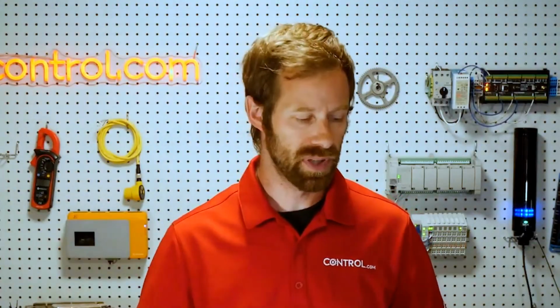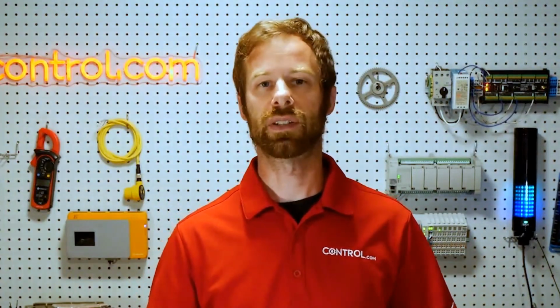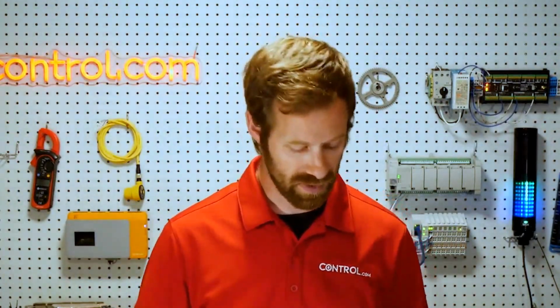So it's always really important to take a look at those datasheets before we decide for sure which sensor we're going to need. But the three most important are the constant positive and negative voltage, but then also that NPN or PNP signal that's the communication between the sensor and the PLC, and that's part of what we're talking about today with one of the most common connection technologies across the world of sensors.